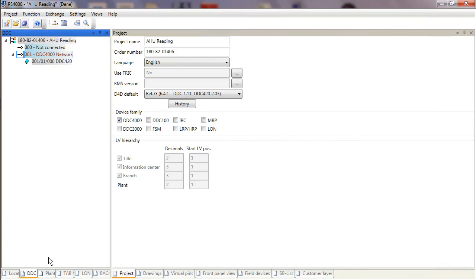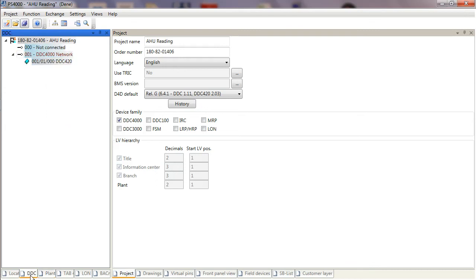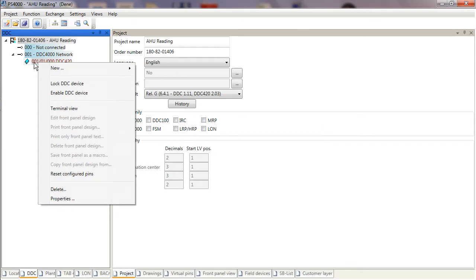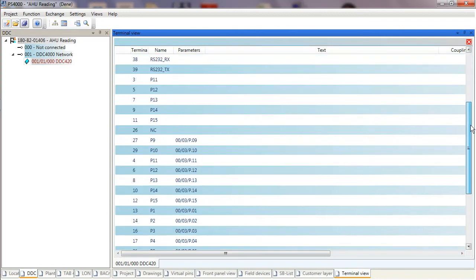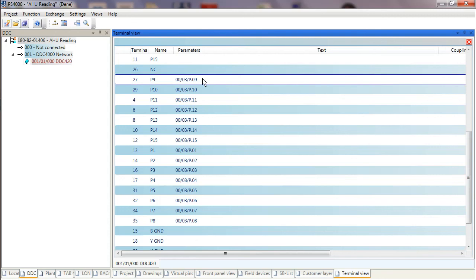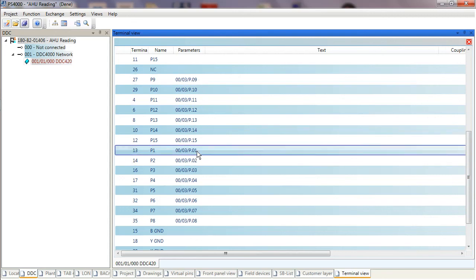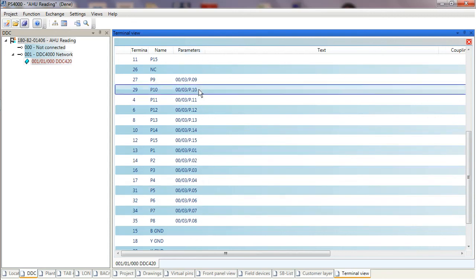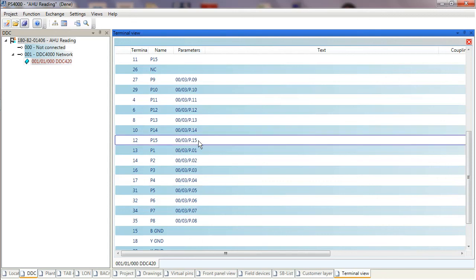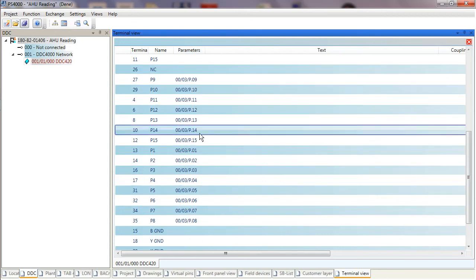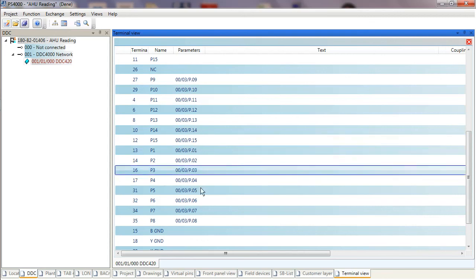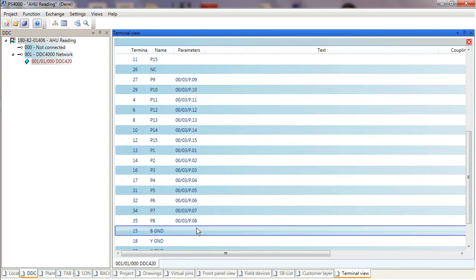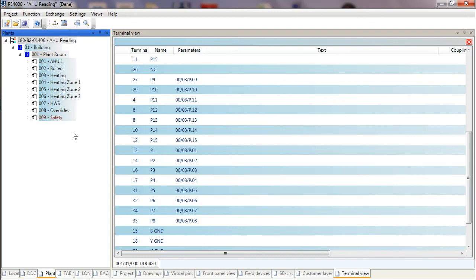Now we are in a position where we can start to allocate some of this point data onto our controller. To do that, I can right-click on the controller I want to program and select Terminal View. This will produce all of the terminal connections that are available on the DDC 420. Here they are—pin numbers 1 to 8 and then 9, 10, 11, 12, 13, 15. Pins 9 and 10 are digital inputs, 11 to 15 are binary outputs, and pins 1 to 8 are universal, so they can be binary inputs, binary outputs, analog inputs, or analog outputs. They can also be used for meter points for pulse counting should you want to do that.